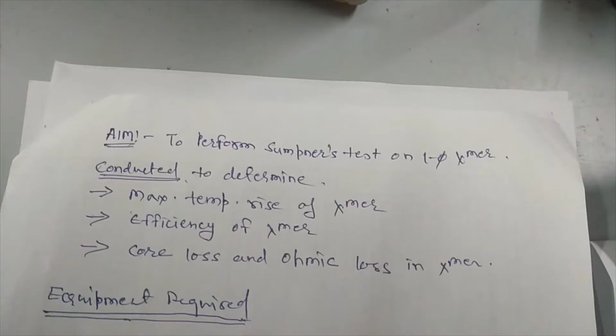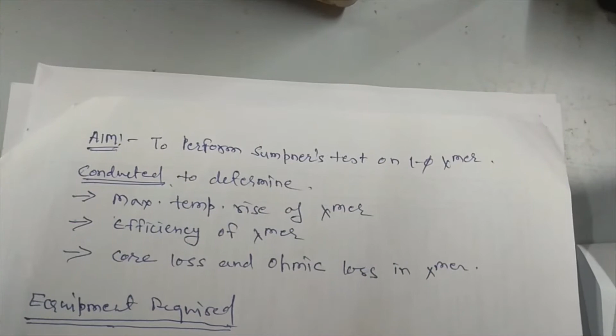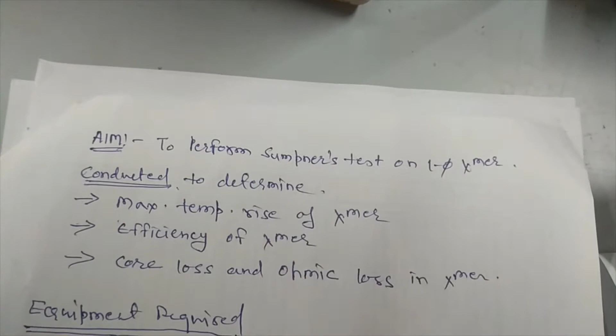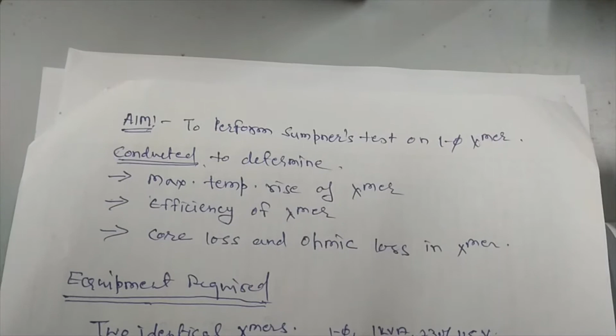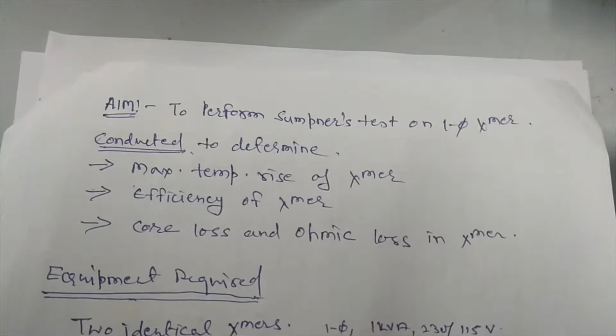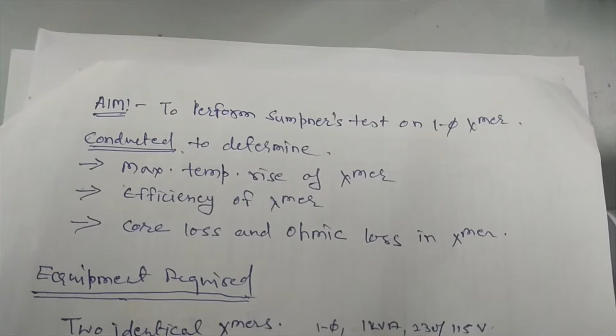Today we are going to perform the Sumpner test on a single phase transformer in the electrical engineering lab. This test is conducted to determine the maximum temperature rise of the transformer. It also provides the efficiency of the transformer, and the core loss and ohmic losses in the transformer.